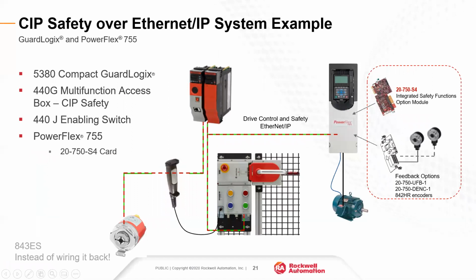Here's another look again, showing the 5380 connected to the 440G multifunction access box, using the CIP safety encoder, communicating over CIP safety over Ethernet back to a PowerFlex 755 with that integrated safe torque off card in there.